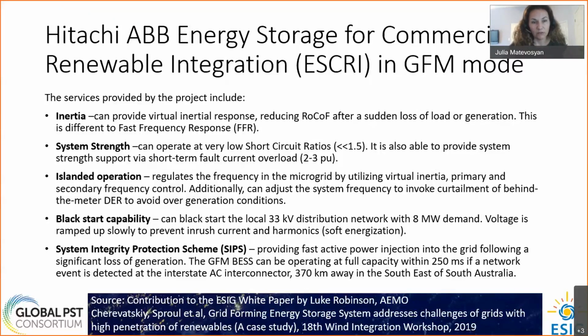As I mentioned, it can do islanded operation, regulates frequency of the microgrid using virtual inertia. It also provides primary and secondary frequency control. It can adjust system frequency when there is over generation on that island system by increasing system frequency, and that causes distributed PV to trip offline. So this way it can regulate against over generation on an island when operating in island mode.